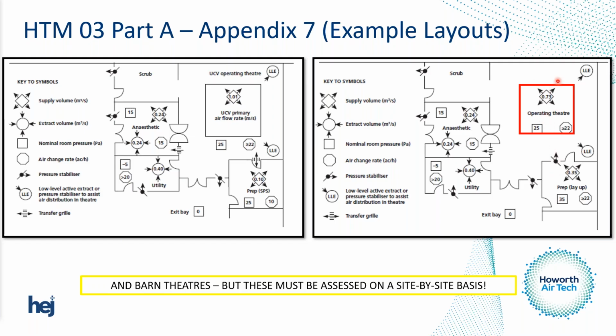So in this instance, if we put a UCV theatre in and the overpressure is right there, this canopy will fail the non-entrainment test. We need to ensure that this is in a satisfactory position to overpressure into the operating theatre, and we need to consider how we're going to baffle that overpressure. So if we speak to the likes of a Preco, they'll be able to help you with that assessment and consideration. It's something that they're very familiar with.